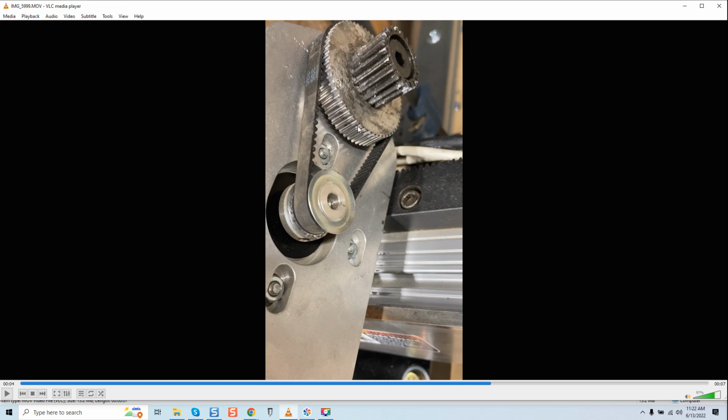Okay, and of course this potential client told me that this system was built by someone else. He went back and revamped the system. But I can tell you right now, I always look for things like this. If I see that the gearing or the transmission of a system is filthy, surface rust, whatever it may be, the first area of concern is this. The machine should be cleaned. And when I say cleaned, it's one thing if you have lubrication in a certain area. When we start seeing debris and black grease everywhere, you already know you're asking for trouble, because that grease over time is going to attract more dirt.